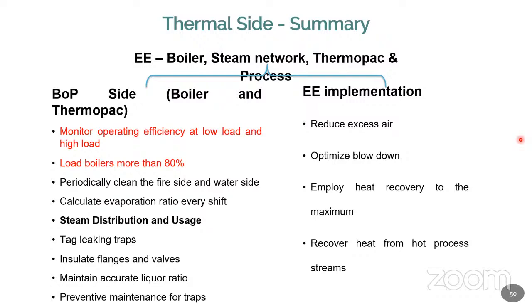Then steam distribution and usage should always be regularly checked. Leakage should always be checked, and insulate the flanges and valves. It is also very important. Maintain the water level accurately. If the water level is very high, it takes more time to produce the steam. When the water level is too low, additional heat will be wasted in the insulation part of the boiler, so that also will be wasted. Okay, so preventive maintenance is to be taken care of for your trapping systems.